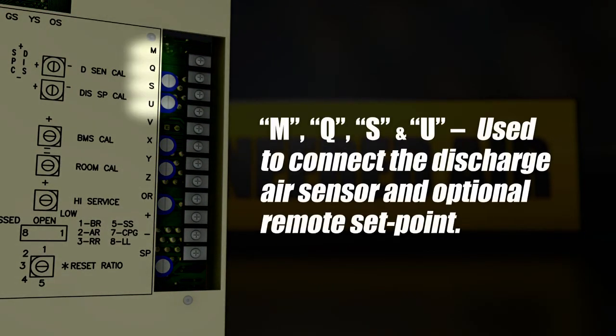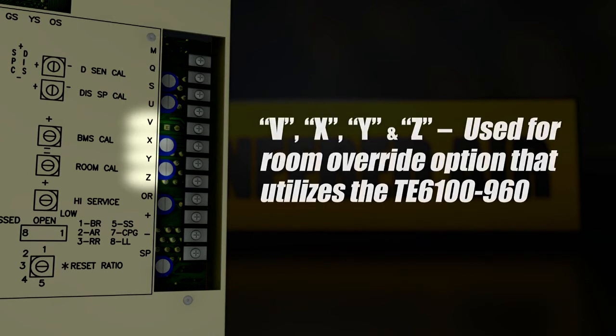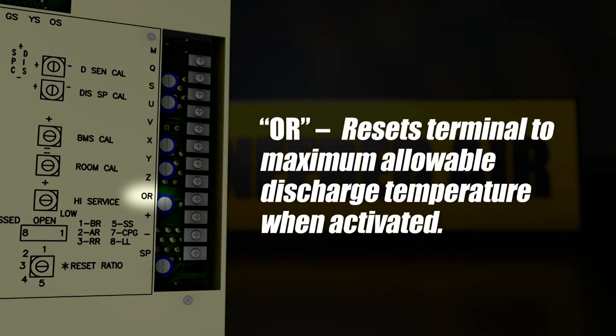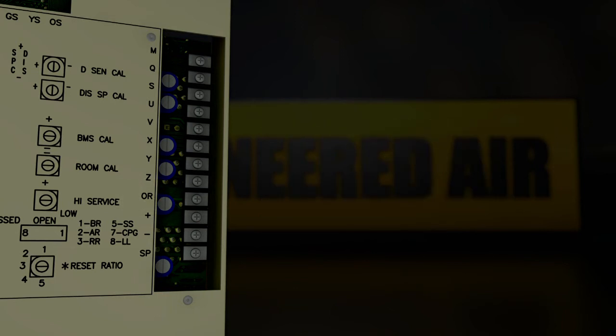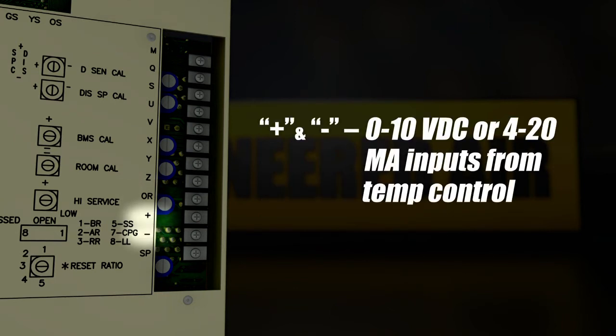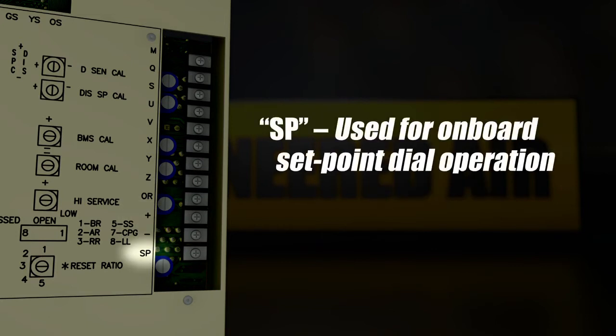The MQ, S, and U terminals are used to connect the discharge air sensor and the optional remote set point if requested for customer convenience. The V, X, Y, and Z terminals are used for room override option that utilizes the Johnson Controls TE6100 960 controller, and the OR reset terminal to maximum allowable discharge temperature when activated. The plus and minus terminals are 0 to 10 volts DC or 4 to 20 milliamp inputs from an external temperature controller. The SP terminal is used for onboard set point operation, and is jumpered to the S terminal when utilized.